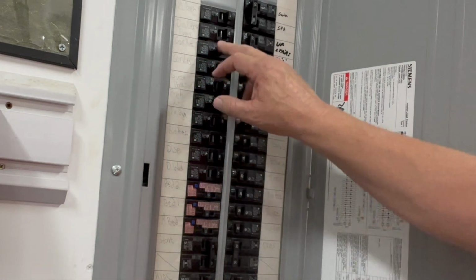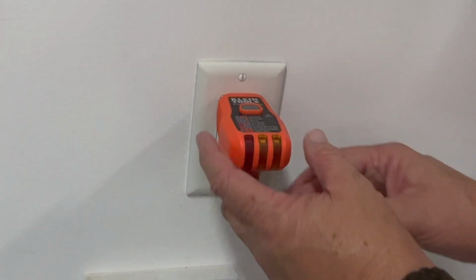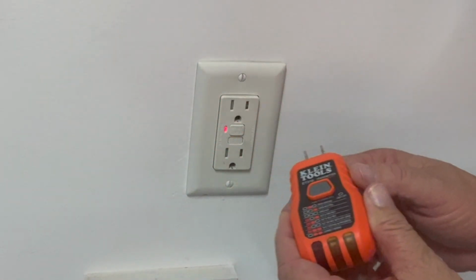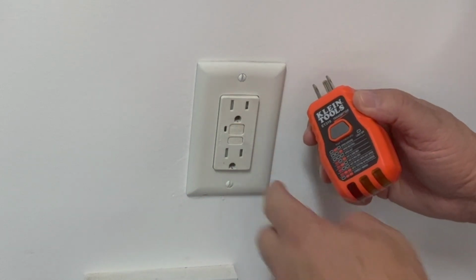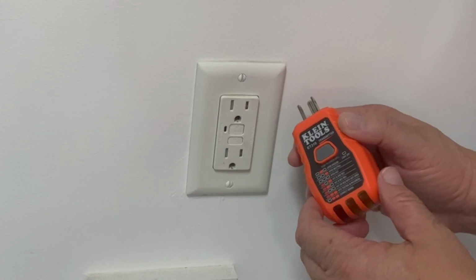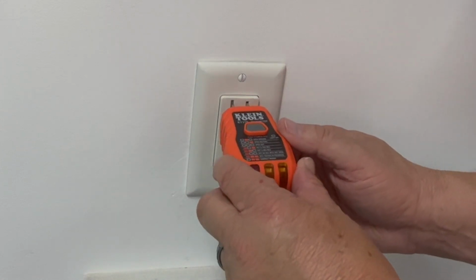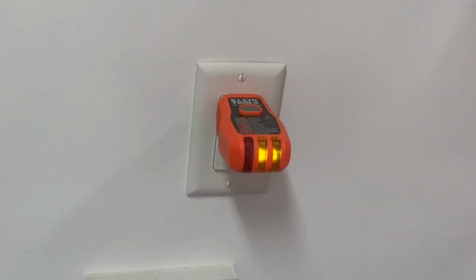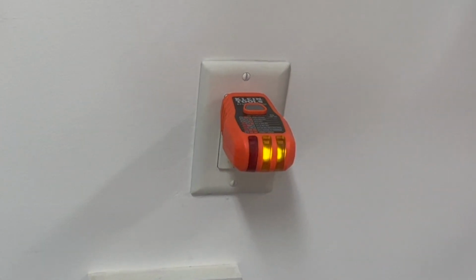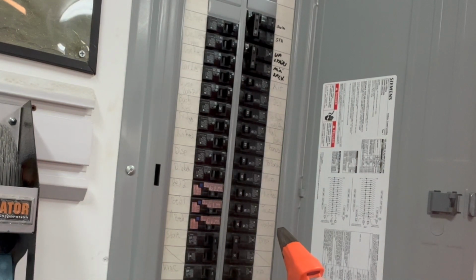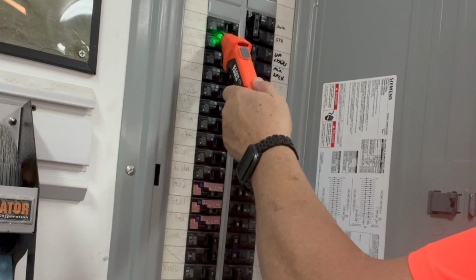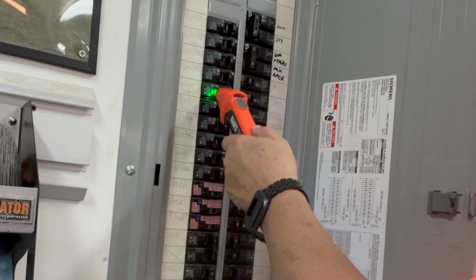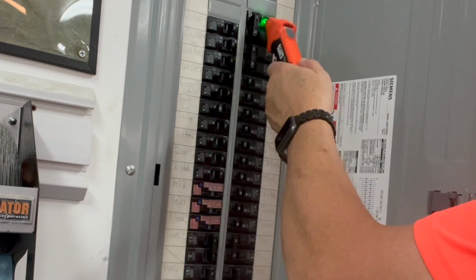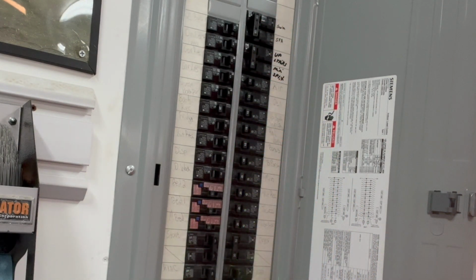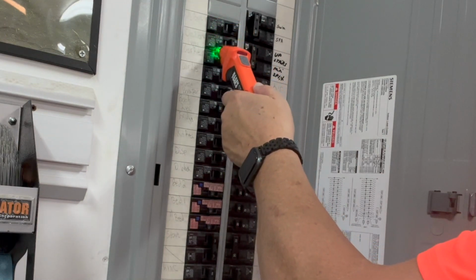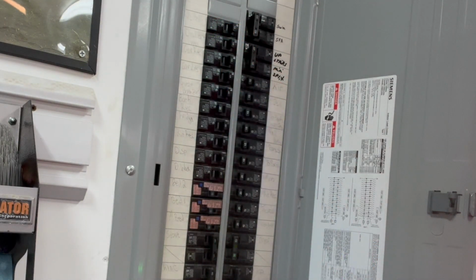So if we turn this back on again, and if you remember, we tripped the ground fault, so you'll have to unplug this and then press in your button again. That reinstates the power, and as you can see, you have electricity indicating there. So we'll go back to the panel. So let's do a final scan on that circuit. Scan once to learn. Scan the second time to identify. Okay, so that's how you identify.